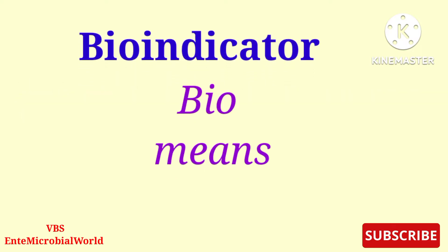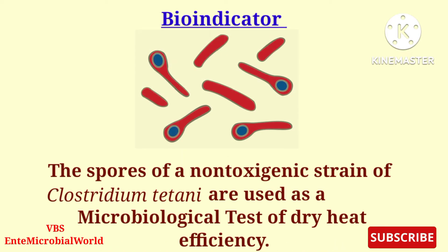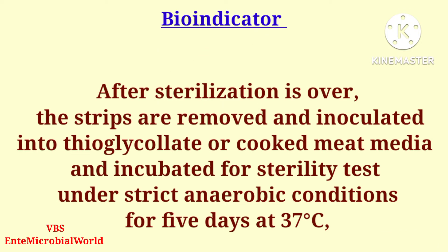First, we are going to look at bio indicators. Bio means life, and here we are using highly resistant microorganism spores as an indicator. The spores of a non-toxigenic strain of Clostridium tetani are used as a microbiological test of dry heat efficiency. Paper strips impregnated with 10 to the power of 6 spores are placed in envelopes and inserted into suitable packs.